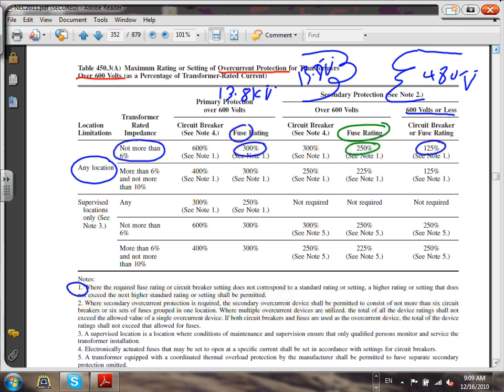Okay, so when do we use this one, guys? We use this one only if the primary or the secondary or both are higher than 600 volts. Listen to me carefully: primary or secondary or both higher than 600 volts. Or, not and, because look here, the secondary could be lower than 600 volts, but the primary is still higher. Any questions, guys, about using this table? Okay, so that's table number 1 that we need to understand.